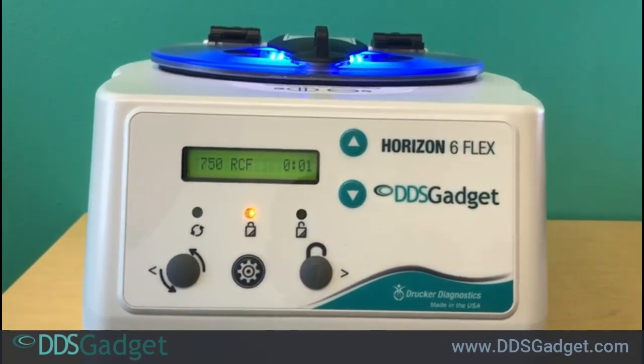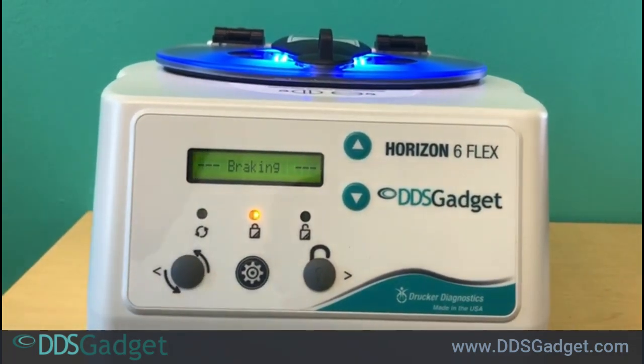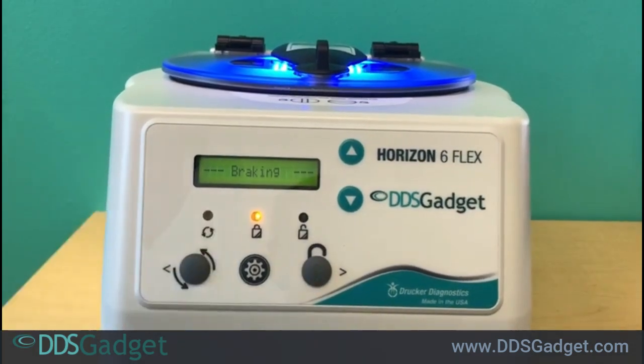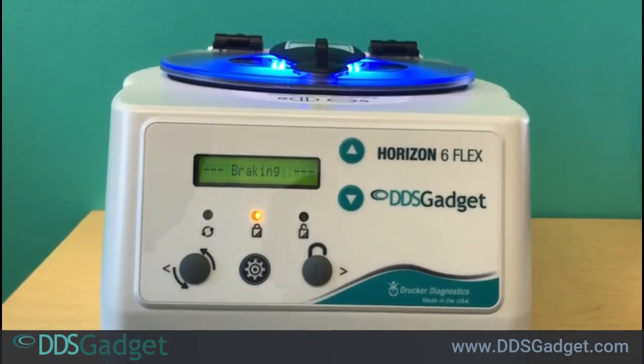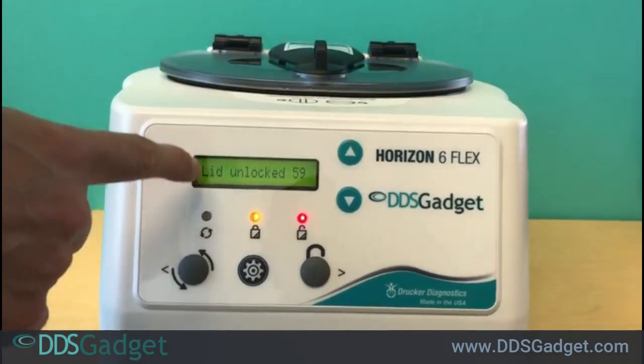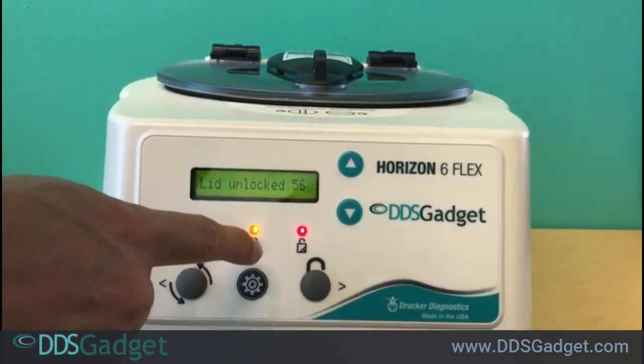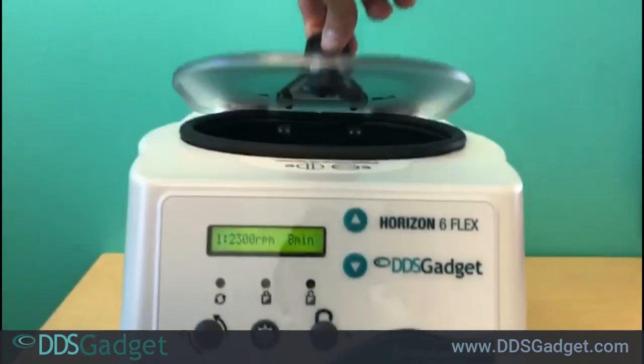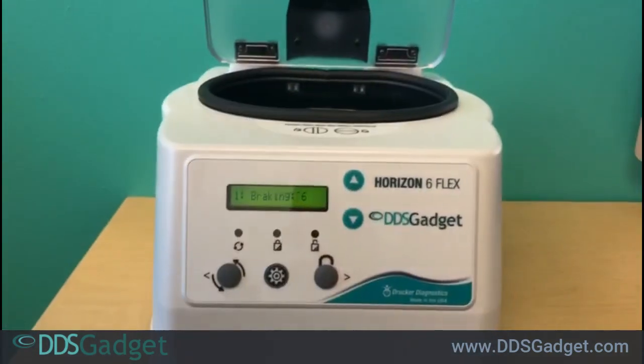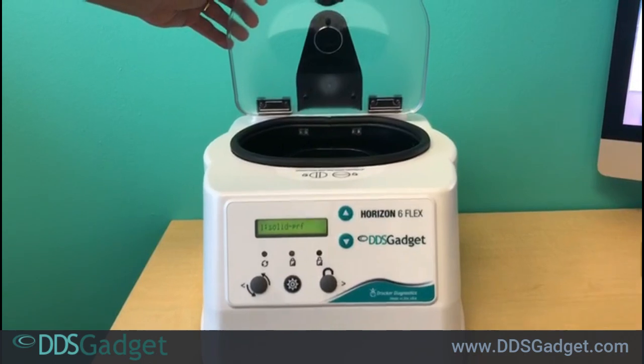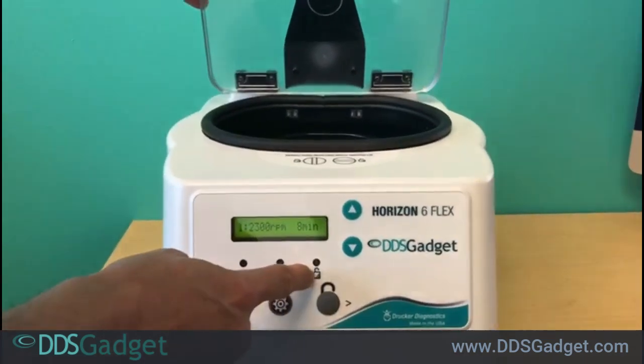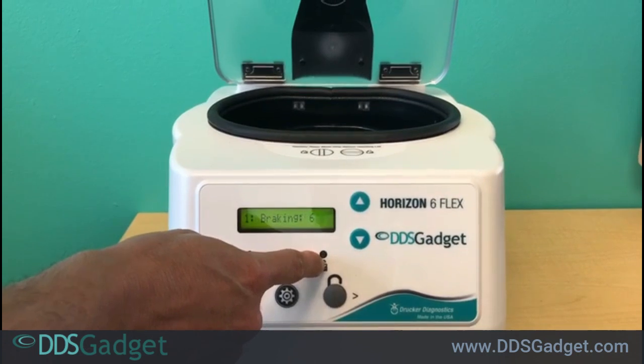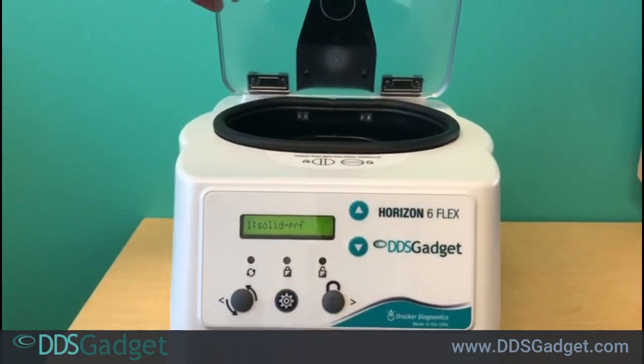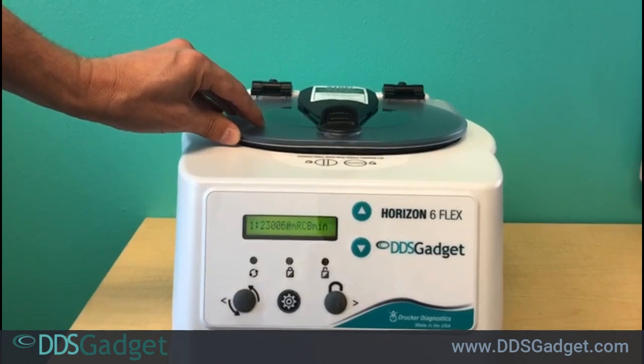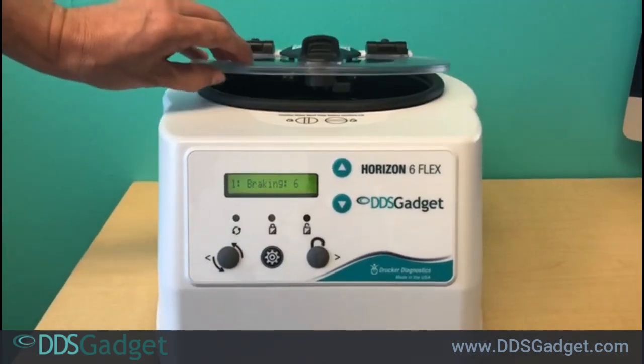And once you hear the beep, and we'll see that right now. So there it says braking. That doesn't mean you can open it yet. It will still say locked. It takes a couple of seconds for it to brake. Now the lid is unlocked. It's at a complete stop. In order to unlock it, you press the unlock button, turn, open it up. So again, at the end of the cycle, just wait till the braking is done and you hear the beep and the light comes on that you can unlock it. And if you don't unlock it within 60 seconds, it will automatically lock again for security reasons. So you have to remember to open it within that 60-second time frame.